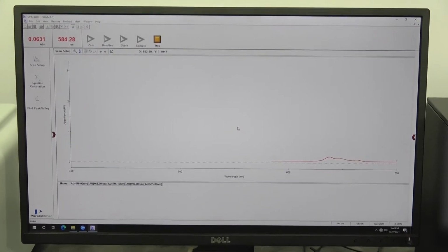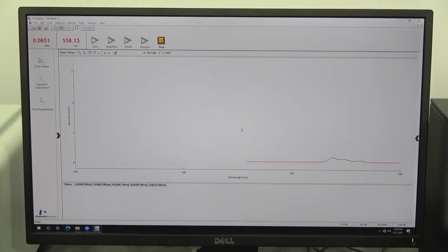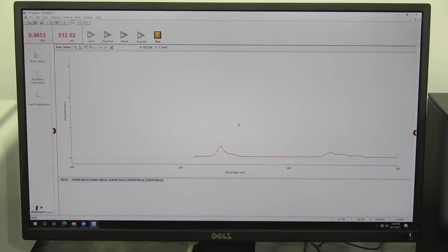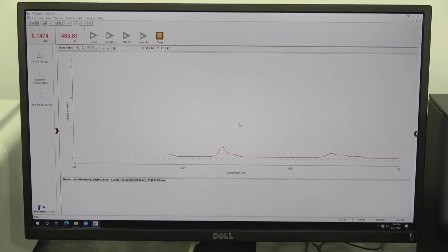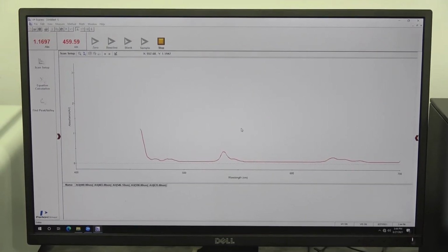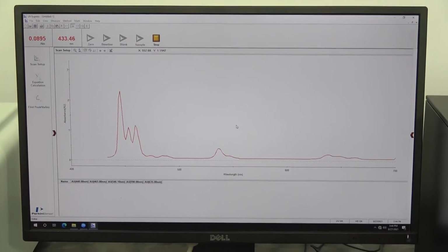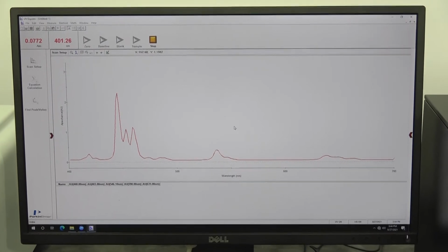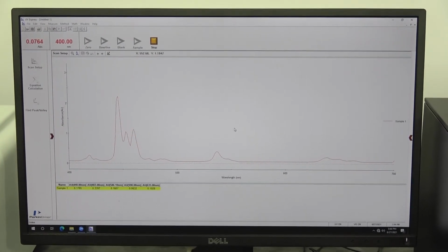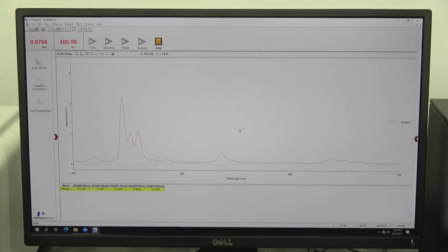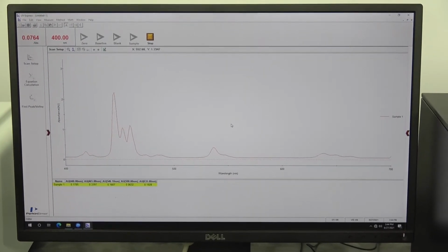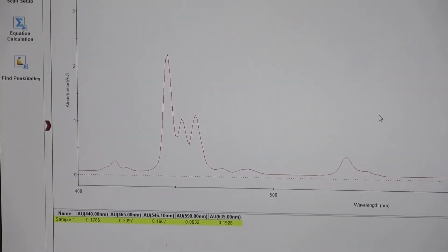You can set it to different settings. Again, very easy to do, just the pull down menu at the top. So very, very well behaved. A lot easier once you get a run to find your peaks and valleys and get some of your data off. That's the changeover to the UV side. And there we get the known peaks of a holmium oxide sample, and we're done.